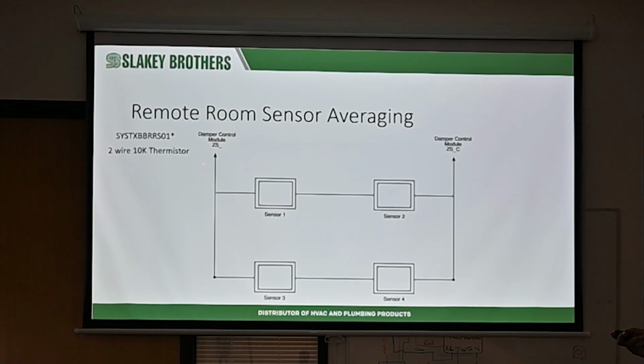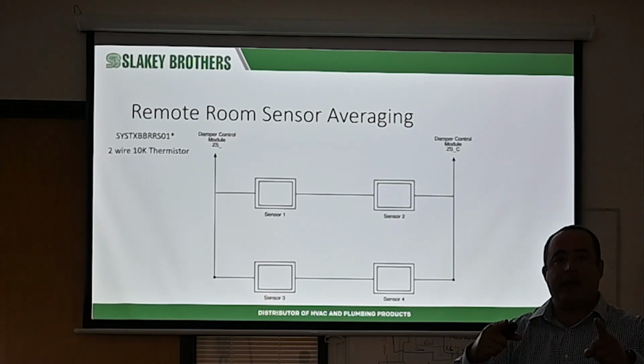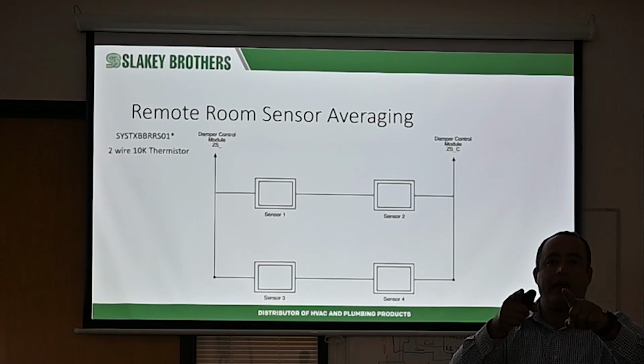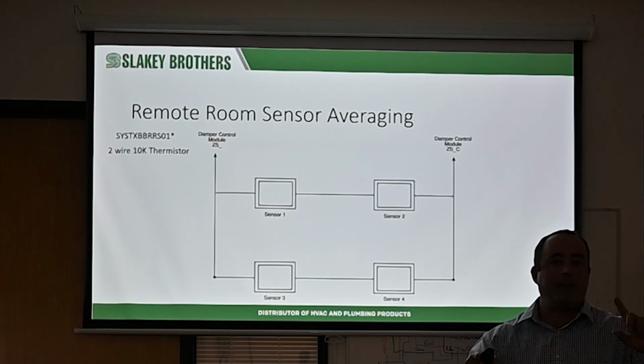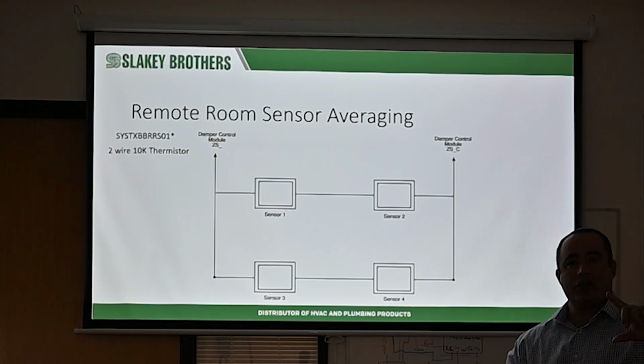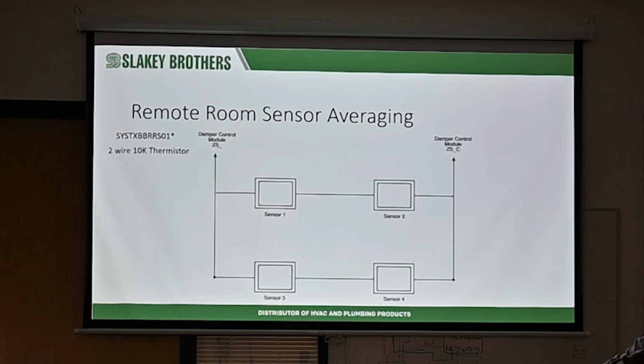And what this will do is they can go back to the zone sensor or to the Connex control, and it's going to just take the numbers out of these 4, and the resistance value comes back as just 1 thermistor average, and the temperature will affect each thermistor overall. So overall, it just averages the temperature on all 4. So if you ever got to do zone average or an average, make sure you use 4.